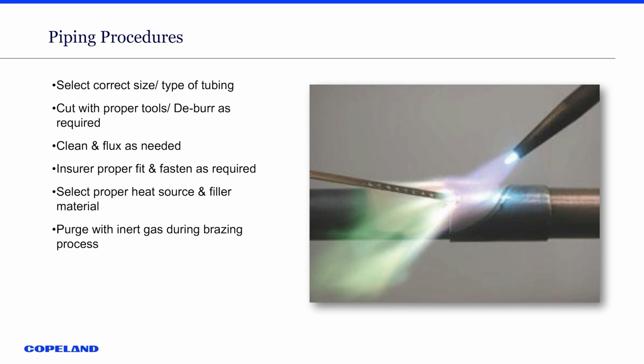All right, so best practices. So a lot of stuff that we'll be going through this next few days will be about best practices and things like that. But when people don't use the best practices on our systems and they're not installing them correctly, our compressors fail, right? So we have to be careful when we're brazing lines together. We have to purge with nitrogen. So nitrogen is an inert gas, so it displaces the air. So for example, if this room were full of nitrogen, it would be kind of hard to breathe, right? Because I need oxygen to breathe.